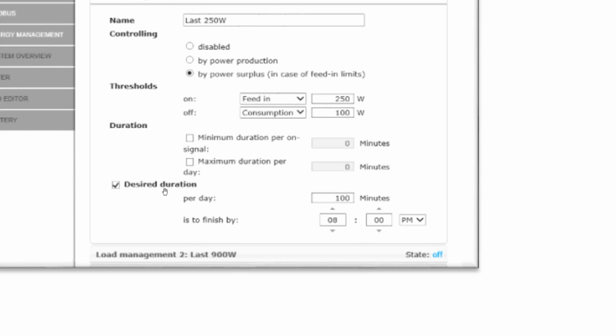You also have to specify what is the desired duration per day, like how long that particular load should be on the whole day. And if it's something that has to be finished within the course of the day, you have to set also a finish by time, so that if you want to be sure that you are going to use as much PV energy as possible, then you set your finish by time to a period whereby you will still have solar irradiation. So like I said, you can proceed like that and be able to set the operation behavior for all the 4 IOs.